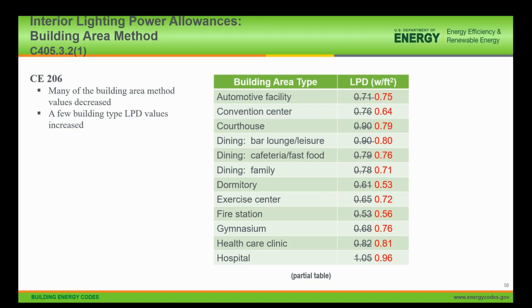The rationale for changes in the values: one has to do with more efficient technology. Some of it is a realignment in the inputs for how the values are developed, either a change in materials, or a change in light levels, which might require either more light or less light depending on what the space requirements are, and the guidance from the Illuminating Engineering Society. So there are multiple inputs that affect these values. Many did decrease because of changes mostly in technology, but I did want to call out a couple of other changes.